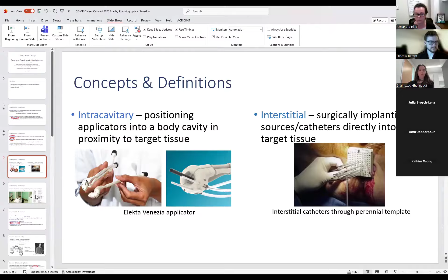Okay, so notice there's no actual radioactive material in any of these things. All of these are effectively voids, or applicators that go inside the patient, but they're hollow on the inside. So how do you get a source inside it? What happens is, in this case, this is connected to something called a check ruler for the purposes of quality assurance. But you can imagine that you can connect these types of tubes, called transfer tubes, to all of the applicators and the catheters that you've implanted into the patient on the one side.